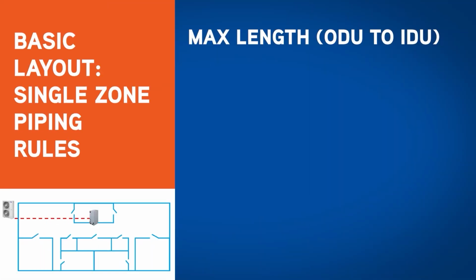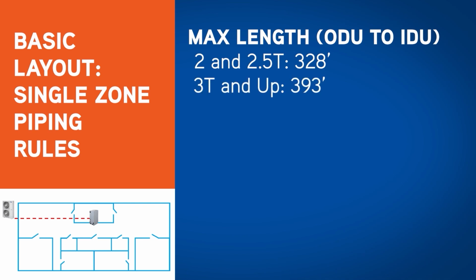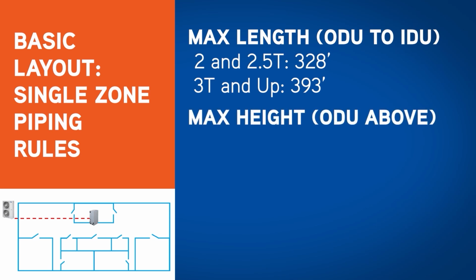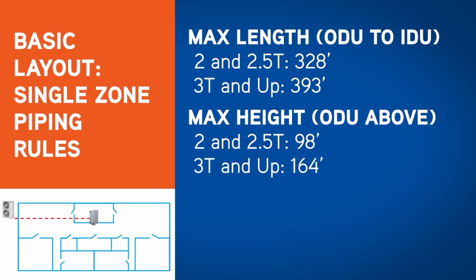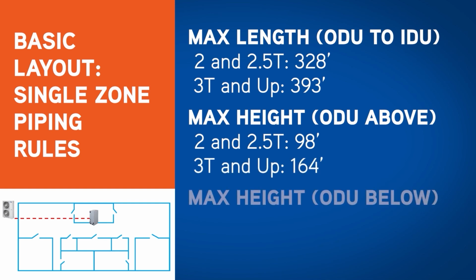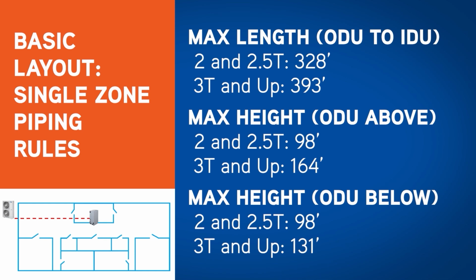The piping limitations of the single zone basic layout are simple. For the 2 and 2.5 ton single zone, the maximum length from the outdoor unit to the indoor unit is 328 feet. For the 3 ton, 4 ton, and 5 ton, the maximum length is 393 feet. The maximum height difference when the outdoor unit is above the indoor unit is 98 feet for the 2 and 2.5 ton, and 164 feet for the 3 ton and up. The maximum height difference when the outdoor unit is below the indoor unit is 98 feet for the 2 and 2.5 ton, and 131 feet for the 3 ton and above.